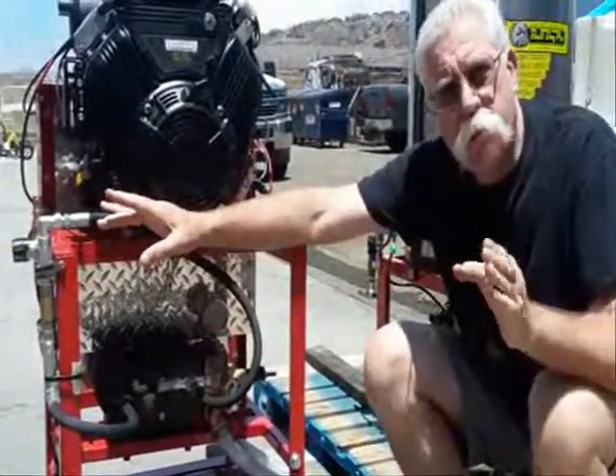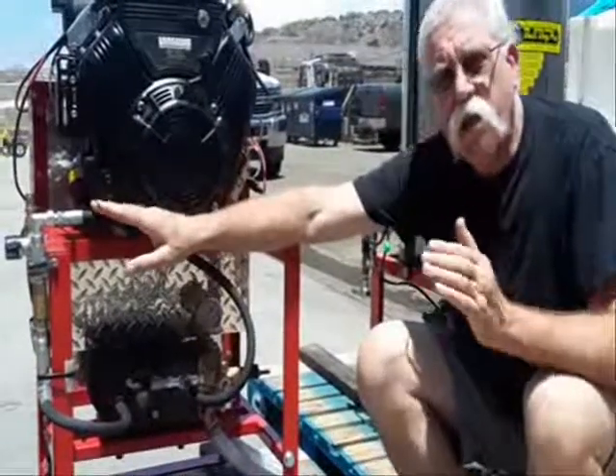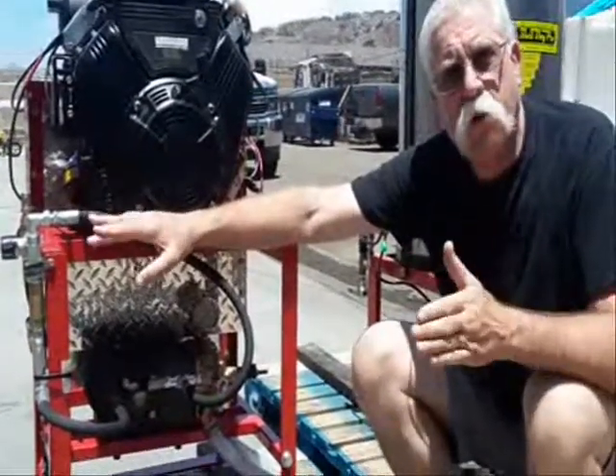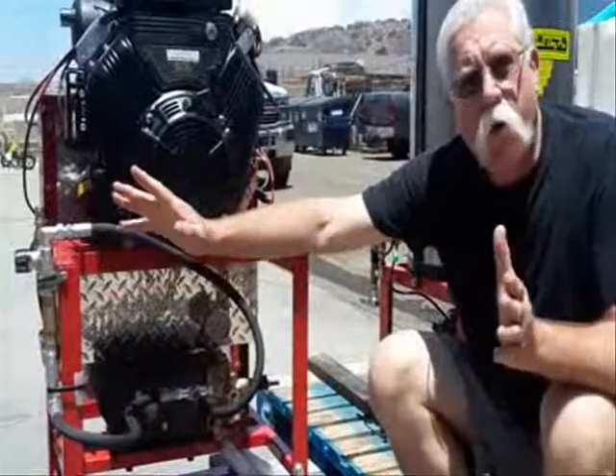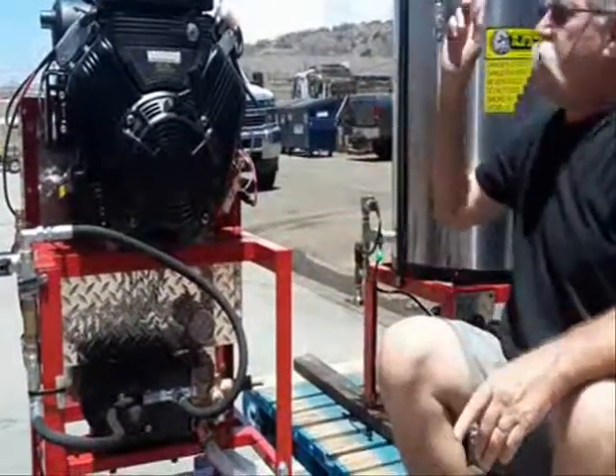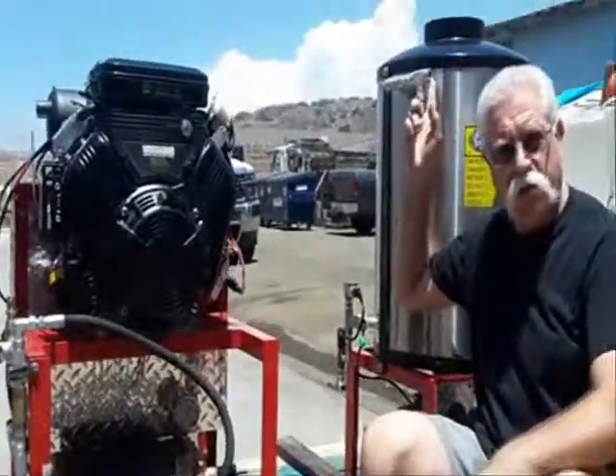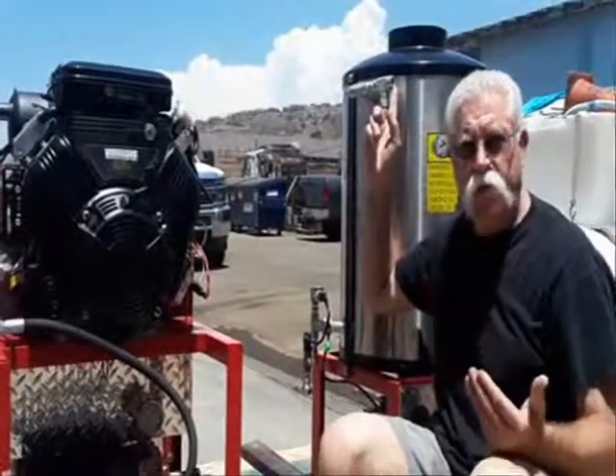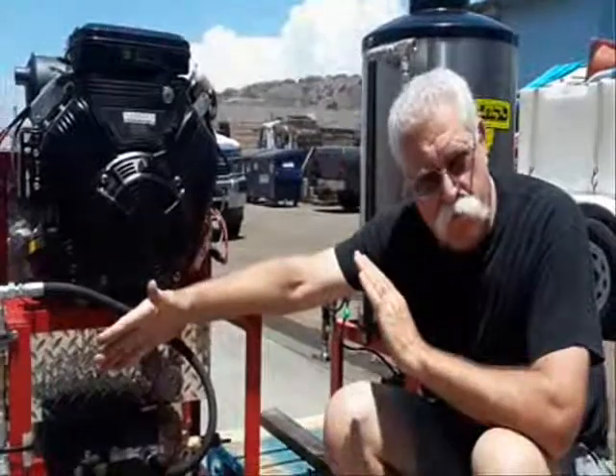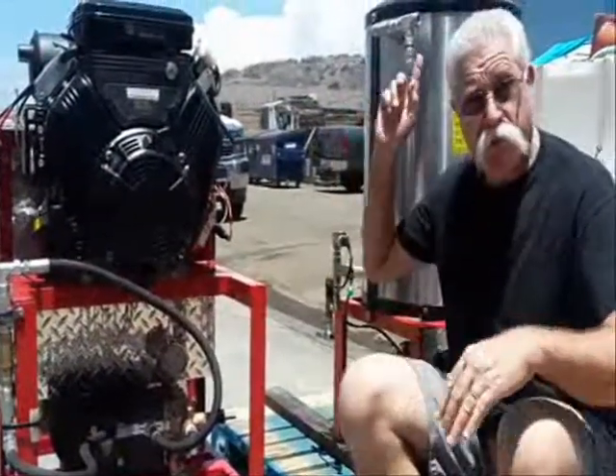Just make sure you're paying attention to the nozzle chart and you're matching the nozzles to the flow of your system so that you're not overheating the water. There's going to be a temperature gauge right here on the outlet of your heater that's telling you what it's really doing. So be aware when you're making adjustments to the flow and pressure that it's also going to change your temperature. Got to watch that like a hawk.